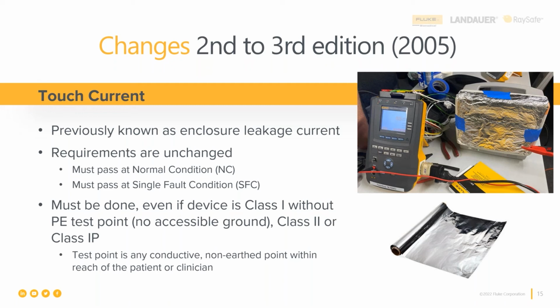So what do you do when there isn't any test point? You just ignore the test? No, you can't. In fact, this test is the one test that must always be done, no matter what. And so if it has to be done, the Standards Committee also has provided guidance for us to figure out how to create a test point for this particular test. Remember that this test point is a conductive, non-grounded or non-earthed point within the reach of the patient or of the nurse or doctor who might touch the medical device and touch the patient at the same time.